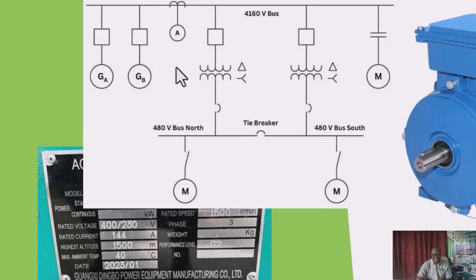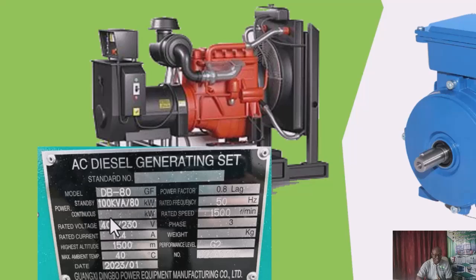So on this single line diagram, which you have seen before in our earlier series, this is the generator through the breaker to the main bus. Okay, so if you look at this bus, you see that the voltage on the bus is 4,160 volts. Okay, that's 4.16 kilovolts. So what this is telling us is that this generator should be able to generate this amount of voltage.